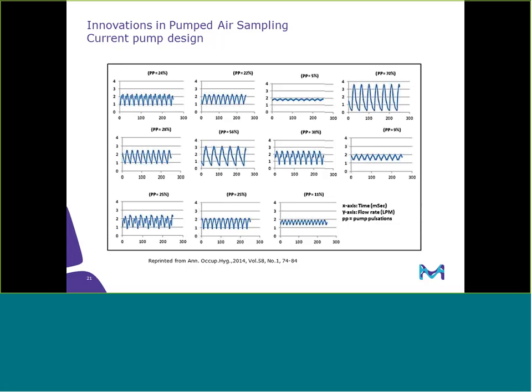Now, how we measure flow rate, how that's calculated by the pump, is certainly questionable, or could be. One pump is certainly not going to calculate it the same way as another one with a different waveform, or hopefully not. And that's why we use a calibration device to actually measure that flow rate pre and post sampling.